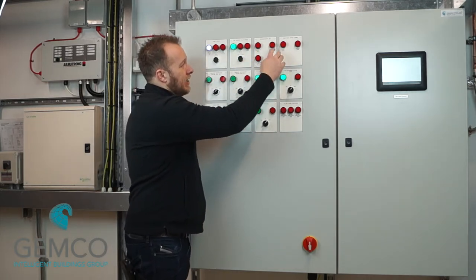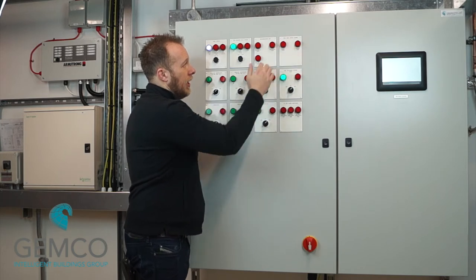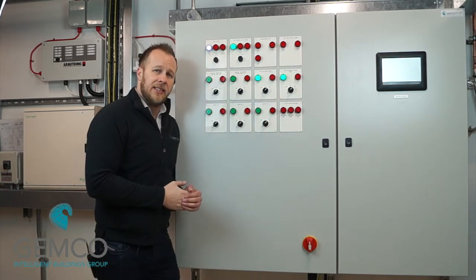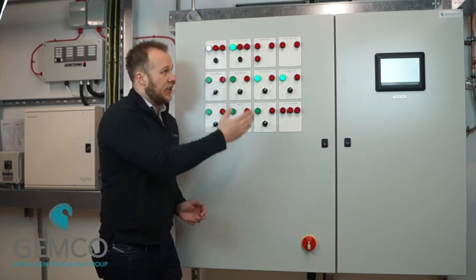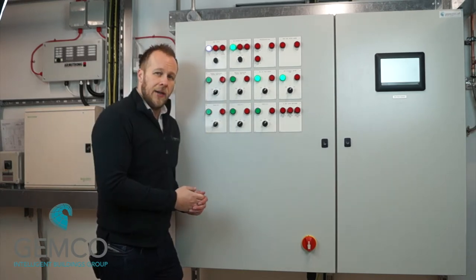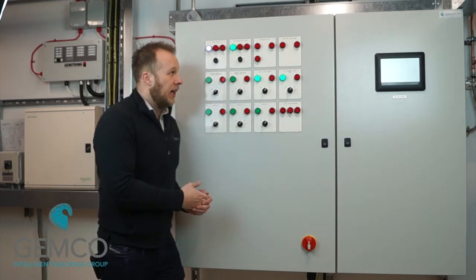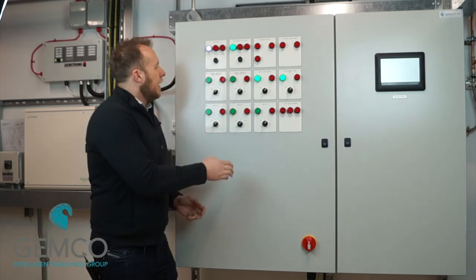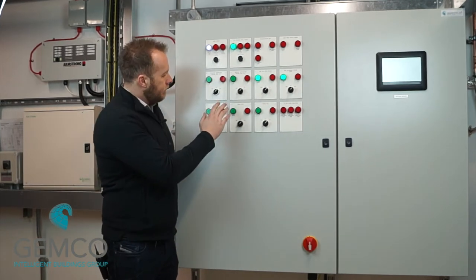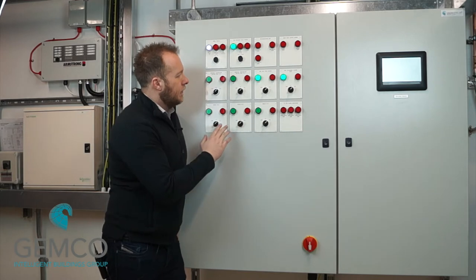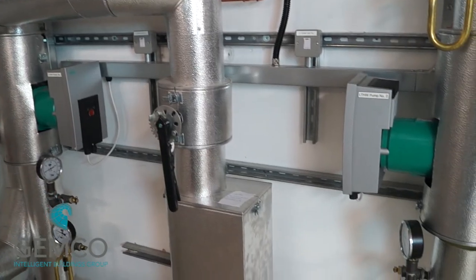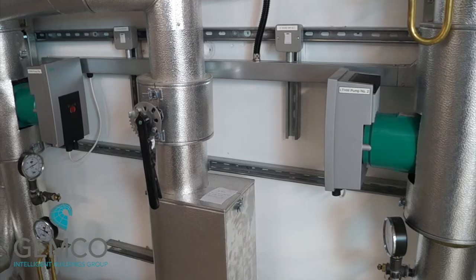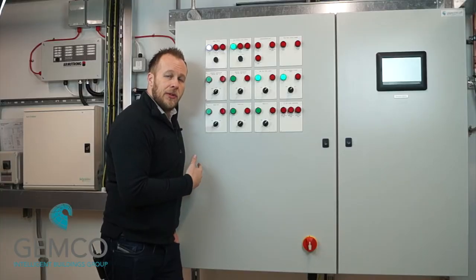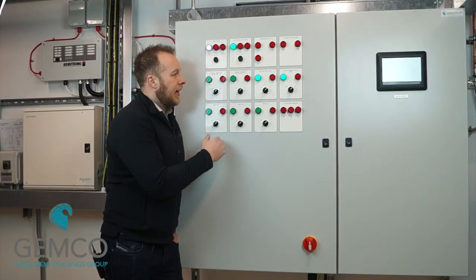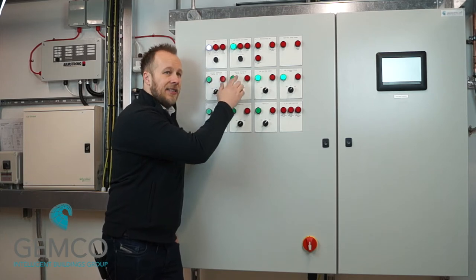Moving on from that, it's just a miscellaneous plant monitoring alarm label, which is for the overdoor heaters. There's a couple of overdoor heaters, and we just monitor the fault from here. We don't control the heaters, but we just monitor the fault on there. Okay, so moving on to the pumps. It's a very simple system. You've got one set of constant temperature heating pumps that serve all of the system, so the radiant panels, the air handling units, and it's a twin set of pumps.